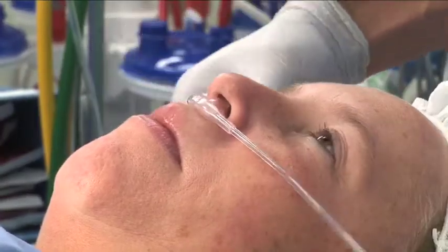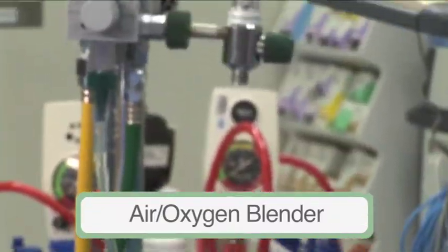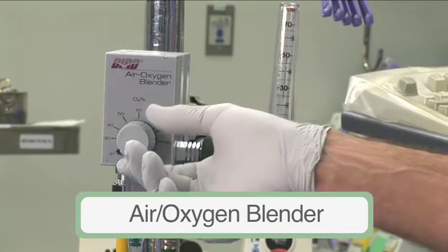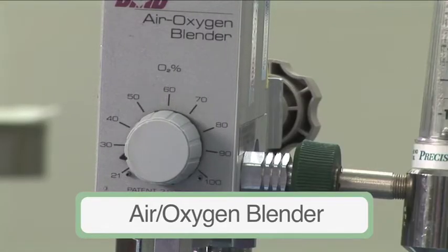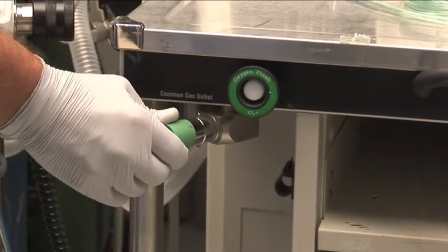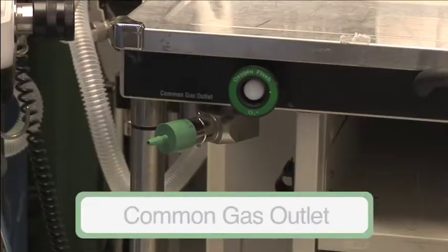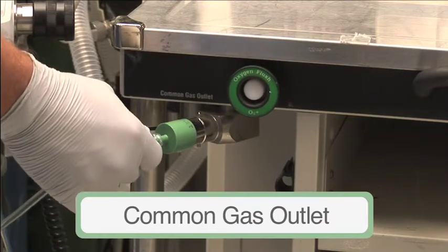Three options are recommended for blending oxygen with air during exceptional surgical cases where open oxygen delivery is essential. The most reliable approach is to use an air oxygen blender to provide the gas to the nasal cannula or mask. The primary advantages are that the oxygen concentration is selected directly and that these devices are accurate. However, although commonly available in other areas of the hospital, air oxygen blenders may not yet be present in many anesthetizing locations. Alternatively, use a 3-gas anesthesia machine, one with air, oxygen and nitrous oxide, that has a readily available common gas outlet, and take the blended gas directly from the outlet.